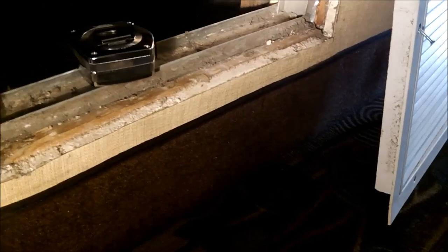All right, here we are at the 510 unit. We've got a grill here - not a filter grill, just a regular grill. You can see the opening - step back - that's a 12 and a half by 18 opening. There is another one back there that's exactly the same. Just because your opening appears to be 20 by 20 doesn't mean your actual opening is going to be 20 by 20. First and foremost, you've got to fix the return, then we can figure out what to do about the repair.